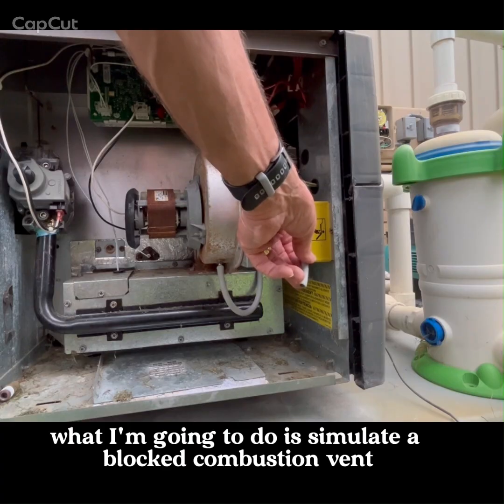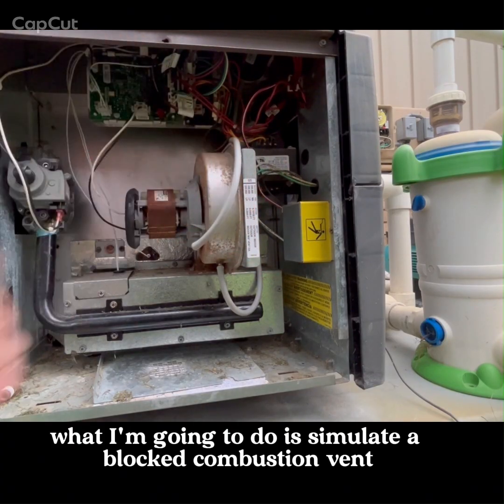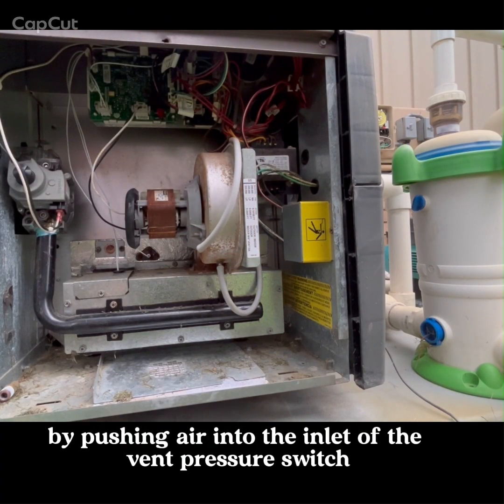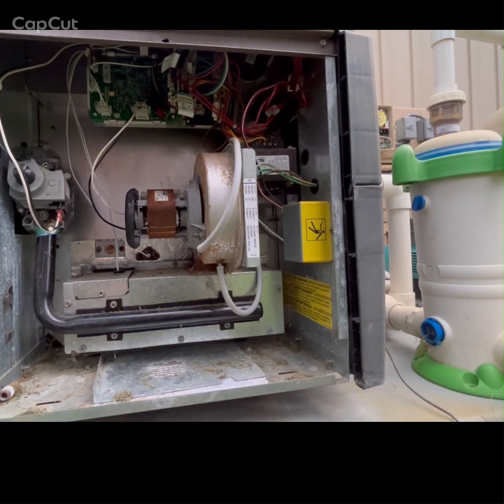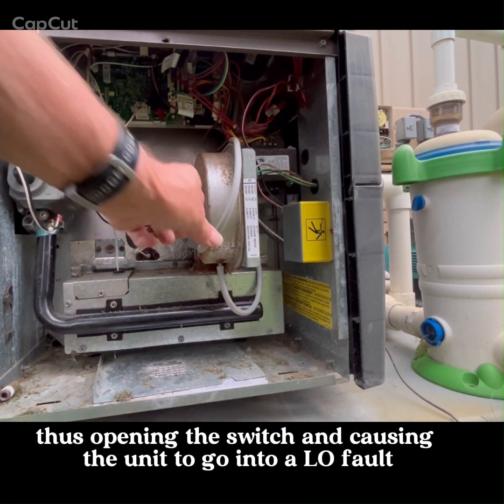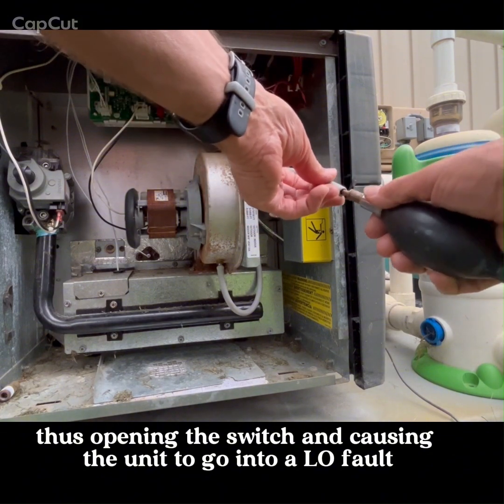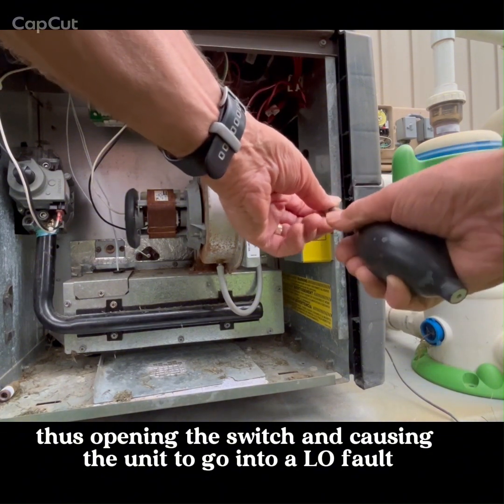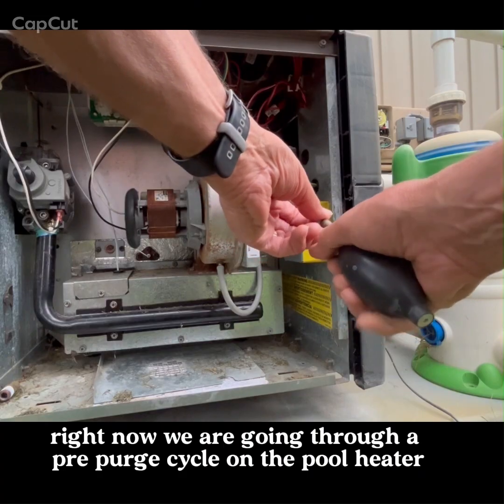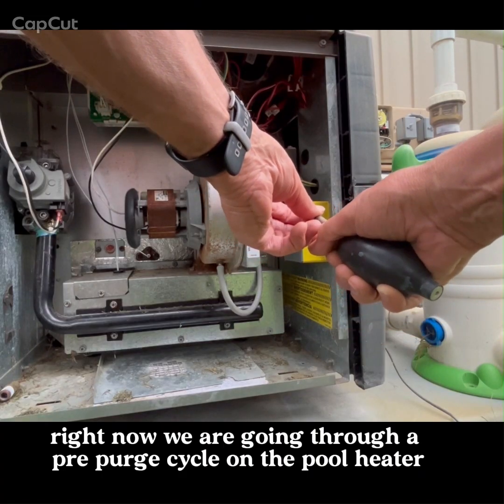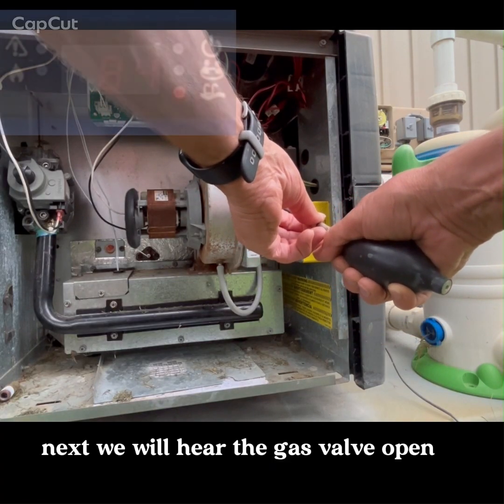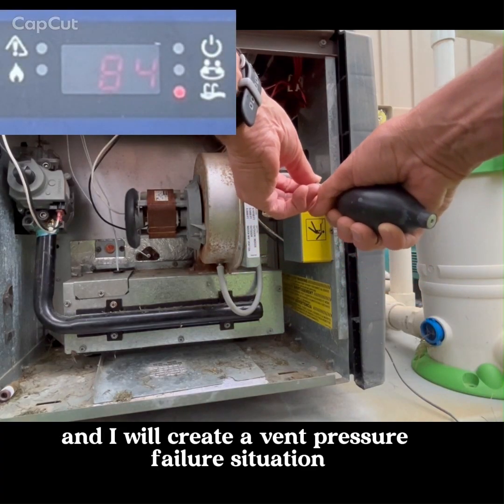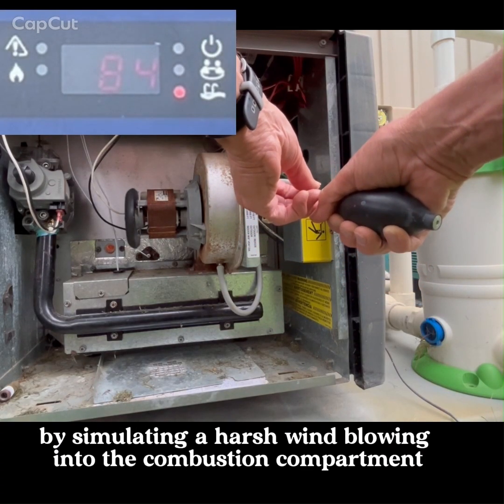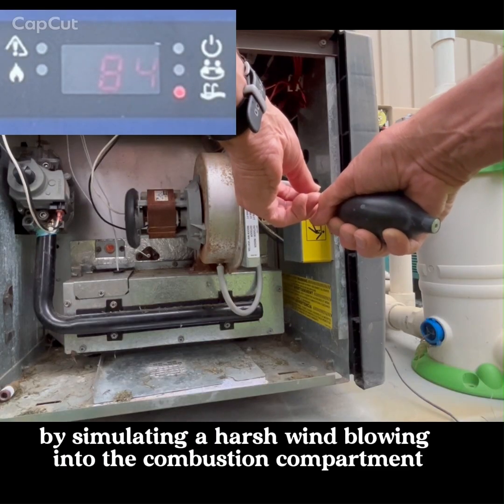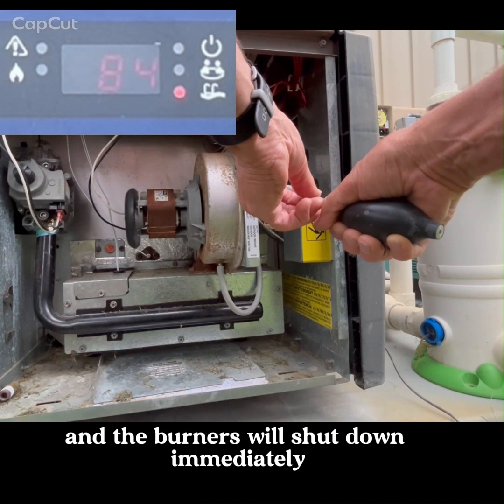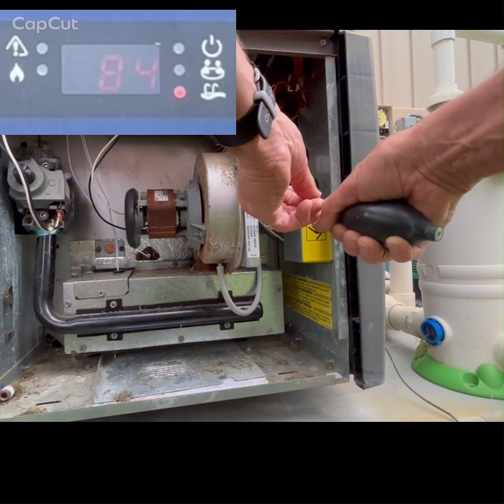What I'm going to do is simulate a blocked combustion vent by pushing air into the inlet of the vent pressure switch, thus opening the switch and causing the unit to go into a LO fault. Right now we are going through a pre-purge cycle on the pool heater. Next, we will hear the gas valve open and I will create a vent pressure failure situation by simulating a harsh wind blowing into the combustion compartment, and the burners will shut down immediately.